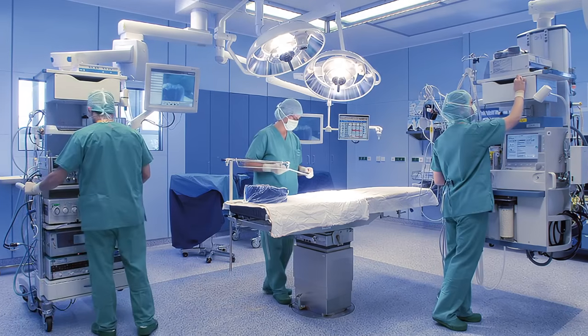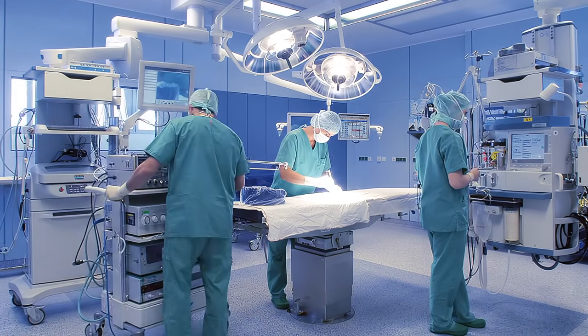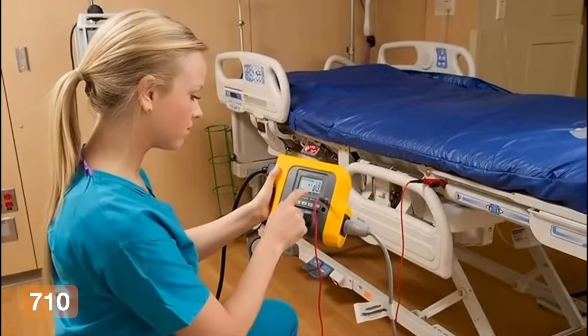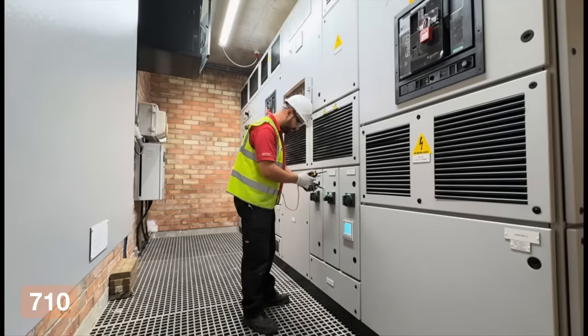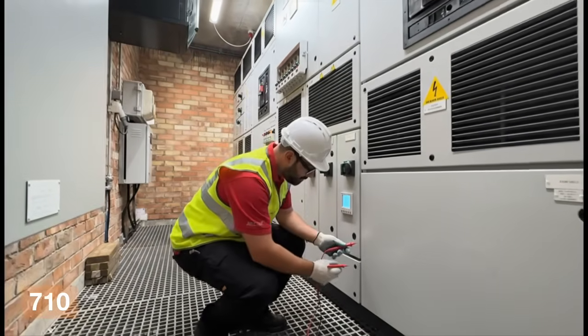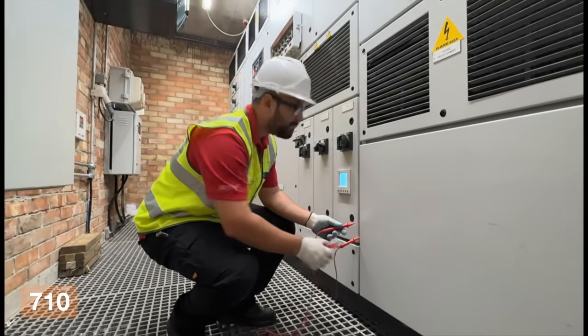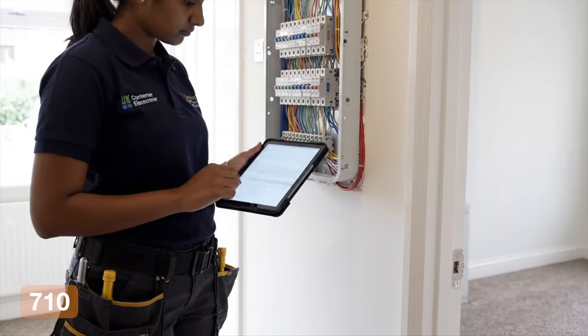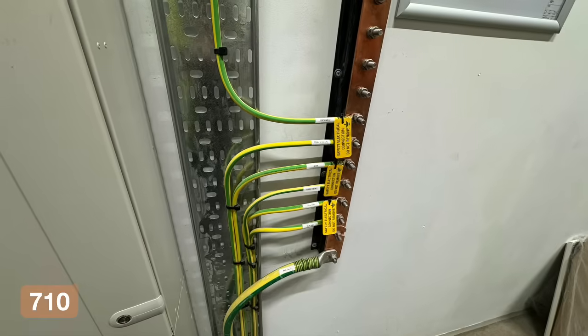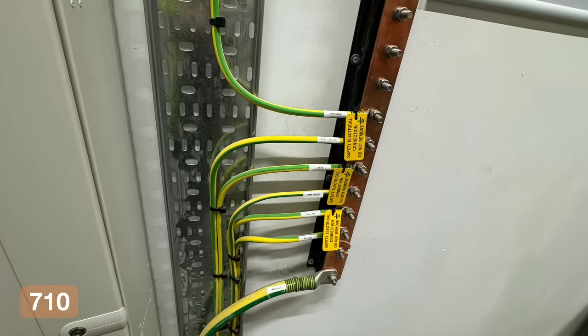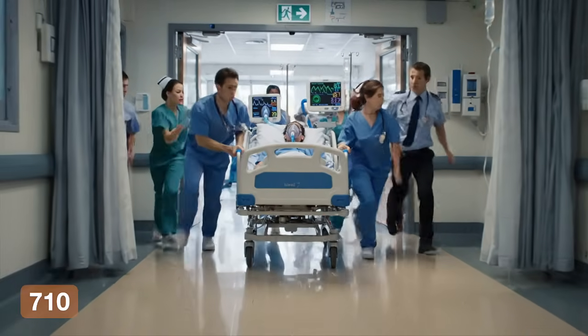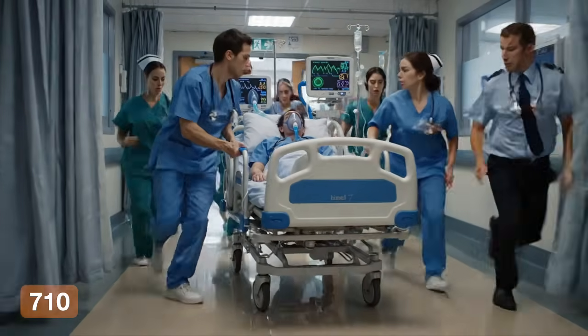There have also been changes in medical locations, even though this will only apply to a small number of installations. Section 710 has been expanded to make requirements clearer and more defined. One of the key changes is around testing and verification. There is now a stronger requirement to record results, including functional testing of insulation monitoring devices and their alarms. So it is no longer just install and assume. It must be tested, recorded, and evidenced properly. There are also tighter requirements around bonding, with defined resistance values that must be achieved. So even though this is a specialist area, the expectation around testing and documentation has been raised.